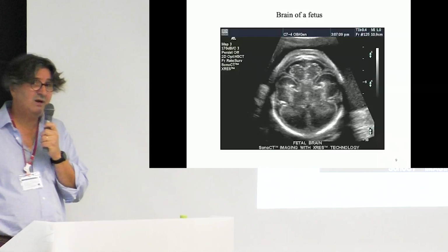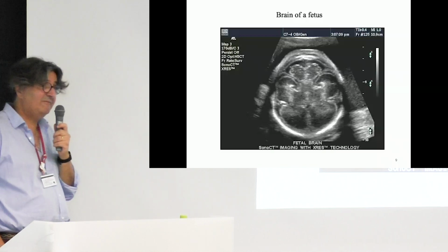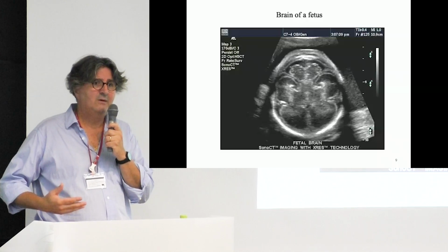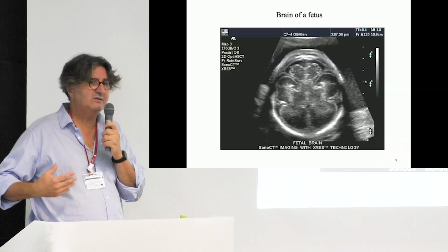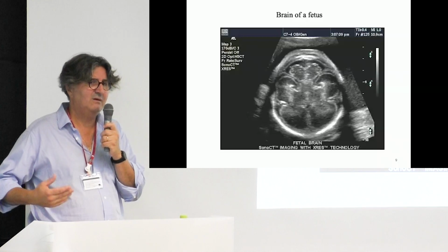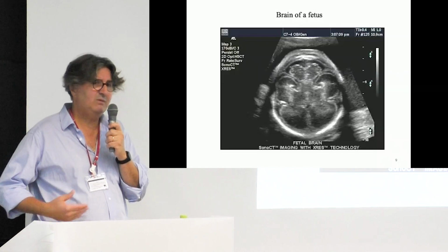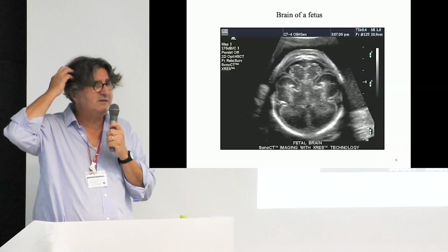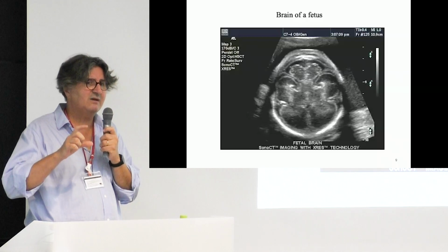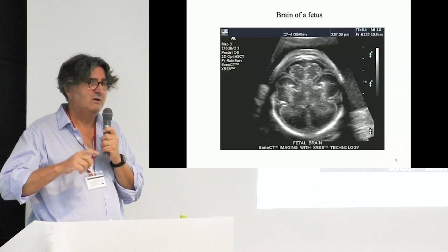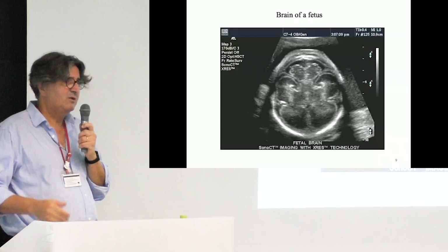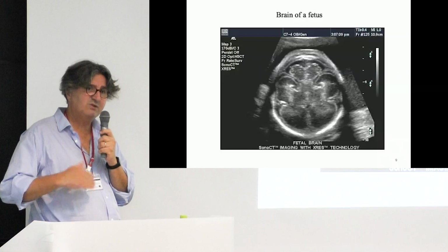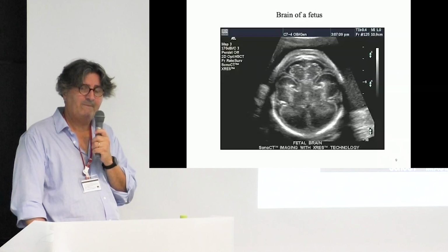There is one point that I would like to underline. We know that soft tissues are mainly made of water, but we don't know exactly the velocity in the human body, because it's a mix. You have tissues, you have water, and so on. So this is an approximate normalized distance according to a velocity. It's not an absolute distance. You may have a bias in your measurement, but it is always the same bias, which makes things reliable.